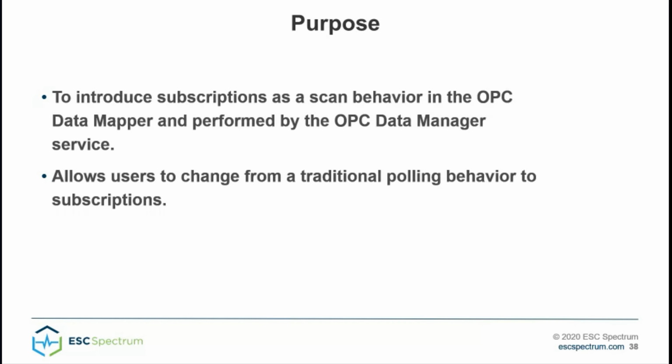A really useful example of this would be calibration expected values or cal gas bottle values, right? If that data is stored in a historian and we want to pull it into StackVision, there's no reason to pull that data once a minute or even once a day. It updates every few years or however long it takes for that to expire or get used. So subscriptions would be the perfect implementation of something like that. Or something where the tag updates frequently enough that we can use subscriptions to pull data.